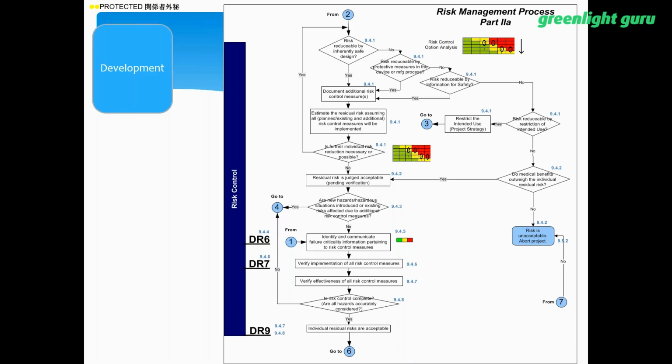And there was a question around what the FDA considers acceptable in terms of ALARP or all of the various as low as practical, things like that. So first off, everybody knows the FDA does not recognize EN ISO 14971 2012 as far as what is practical.